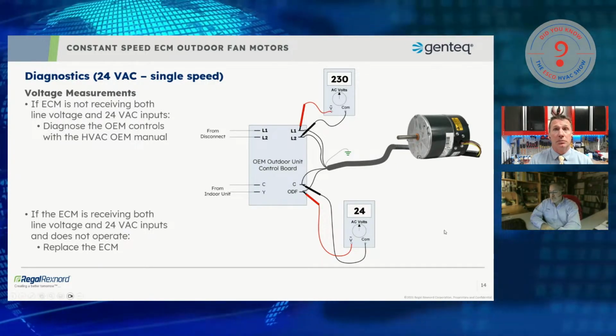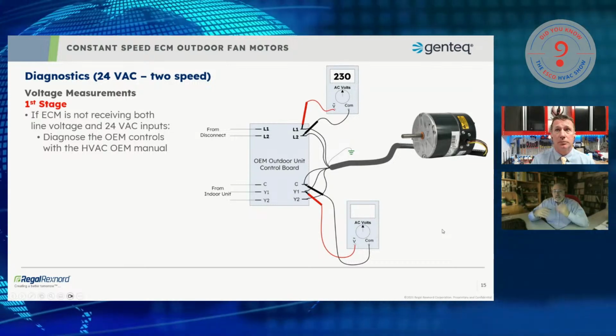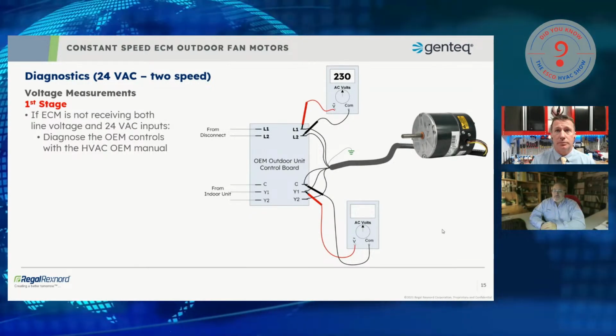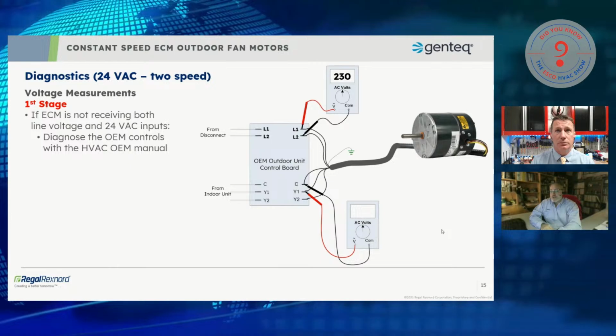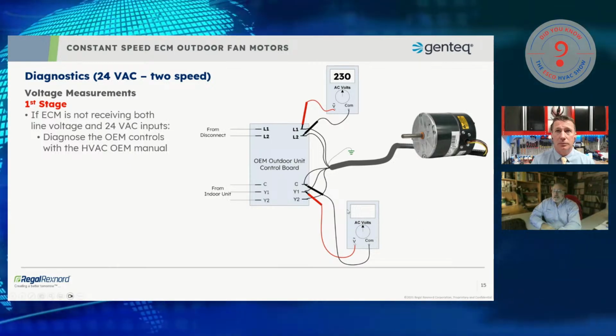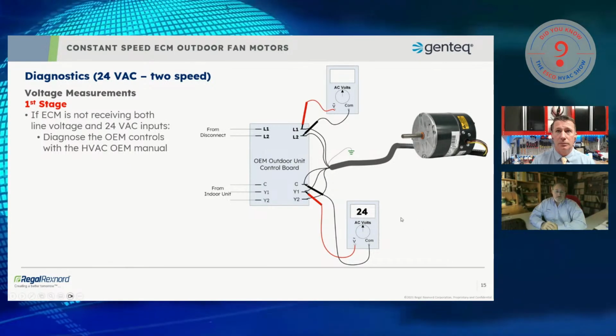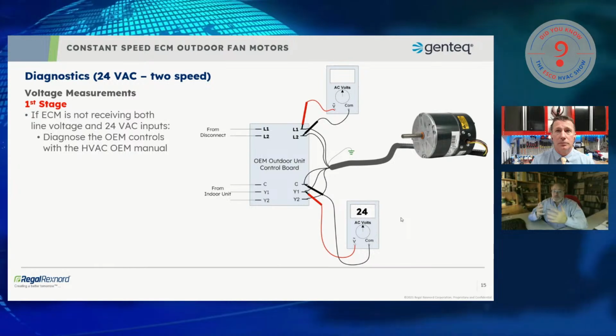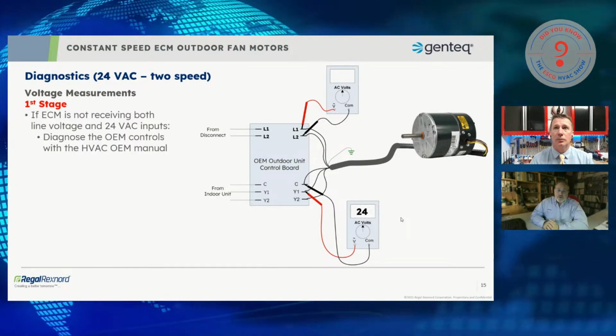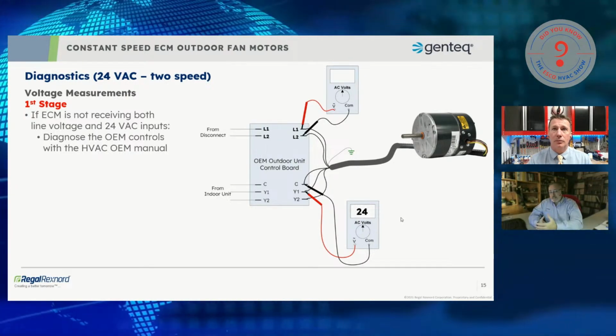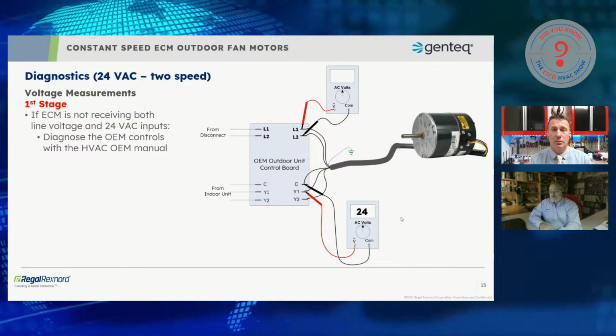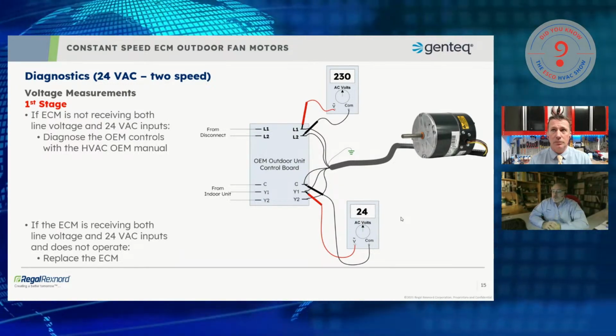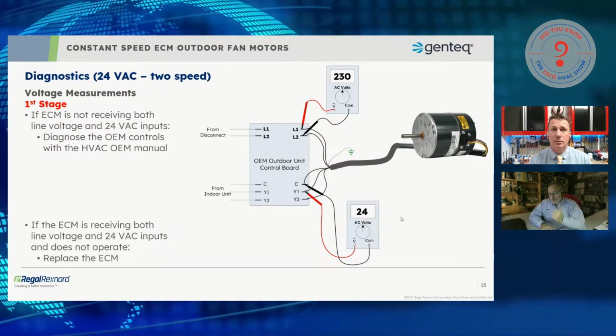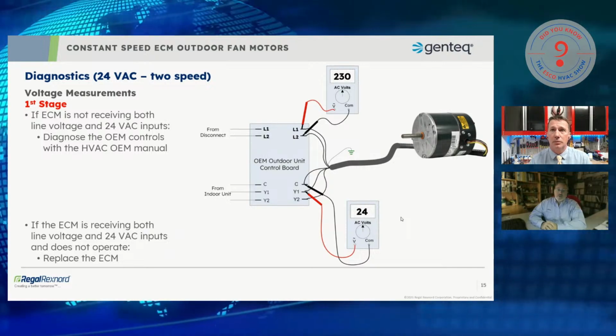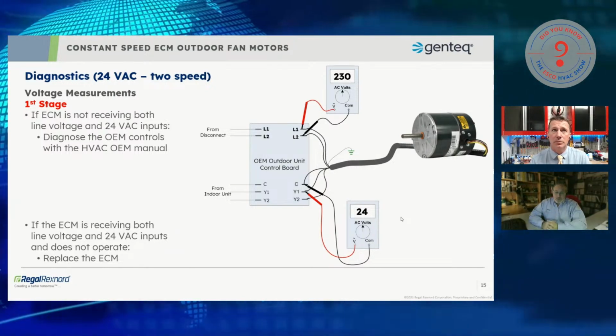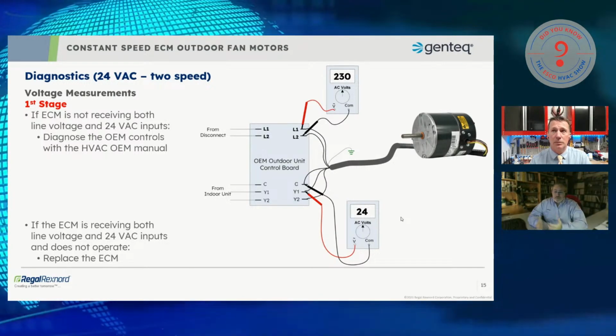So switching gears to the 2-speed, if I'm in first stage, obviously I should have 24 volts on my first stage. But again, before we even get that far, I simply need both voltages for the motor to operate. Regardless of which stage I'm in, I need the line voltage and I need the low voltage for the motor to operate. If I have both voltages and the motor's not operating, the motor's failed. It doesn't matter if it's a 2-speed motor.